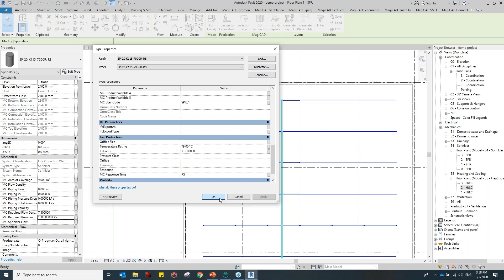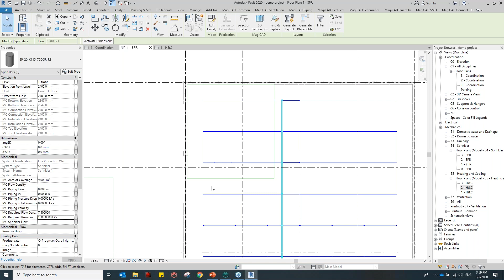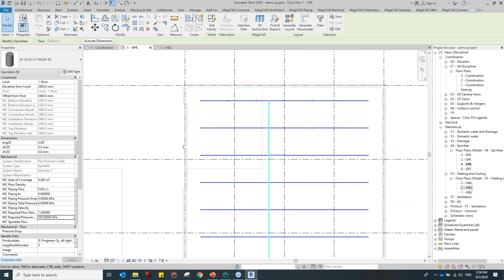In case you are using a normal Revit sprinkler and you want to apply MagiCAD calculations, you can upgrade your normal Revit sprinkler into a MagiCAD sprinkler by putting in this kind of information, and you can perform the engineering calculations with your Revit model as well. It's not that you have to do it in the MagiCAD modeling. We don't restrict you with that, but you have to update some information, and you can perform the engineering calculation here as well. Now I'm done with putting in the basic information, then I can go for a sprinkler calculation.